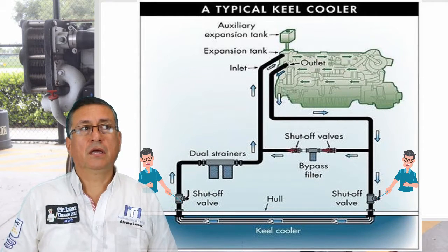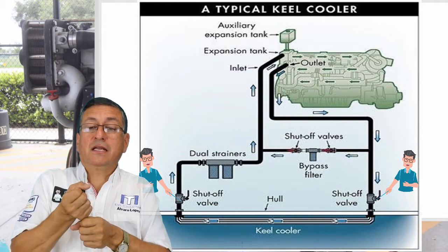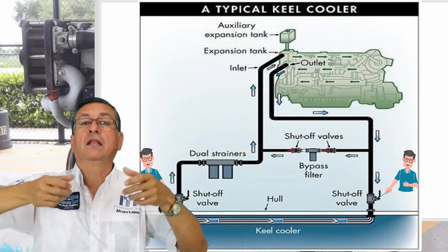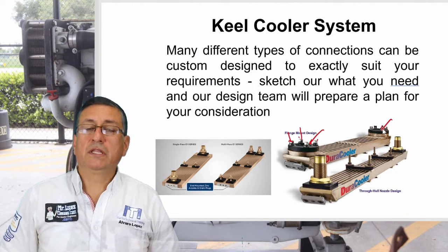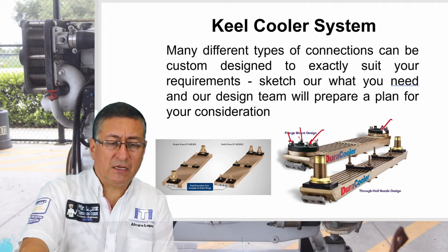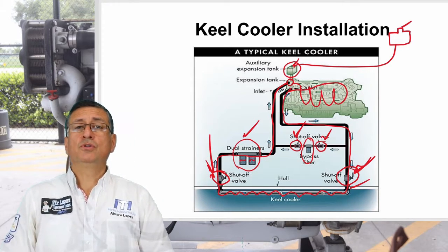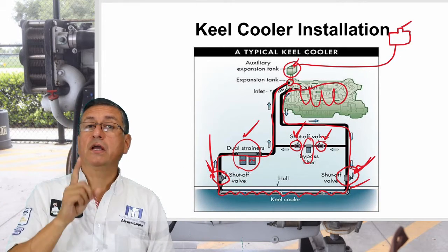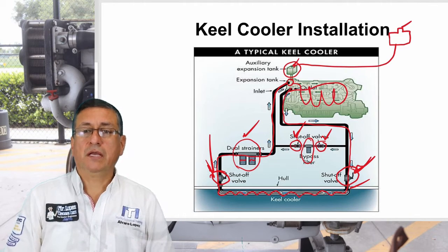In another case, I made a mistake because I turned the handle of the valve, but externally the handle was damaged. The handle moved, but the ball internally never moved, and the valve stayed open. In that case, I spilled a lot of coolant again. Be careful with the valves. Be 100% sure that the valves close properly. What valves? I am talking about exactly these valves, this valve and this valve. You need to close those valves properly before you remove the external radiator. In one situation I forgot one valve. In the second situation I closed the valve, but internally the valve never closed. Be careful with those valves.